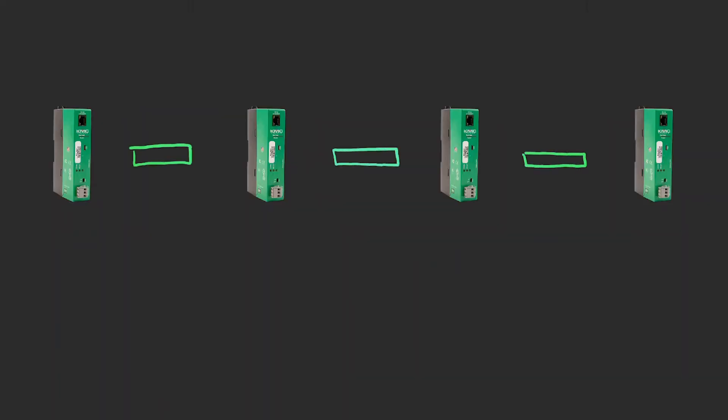Since BBMDs are BACnet routers, all interconnected BBMDs must use the same BACnet network number. With BBMDs, essentially you are creating a BACnet network that only has BBMD devices on it.